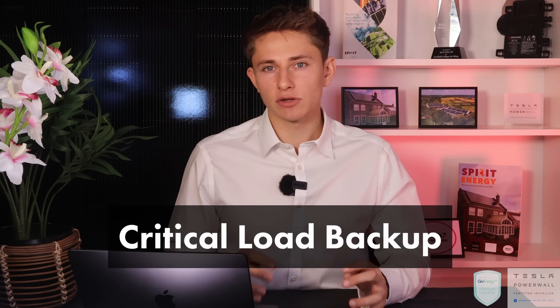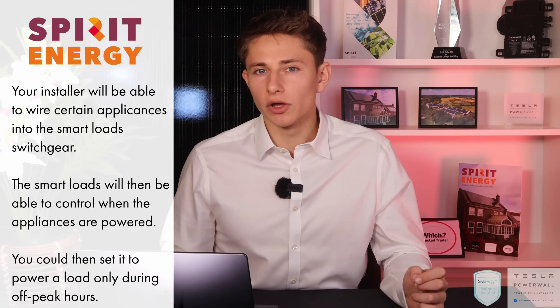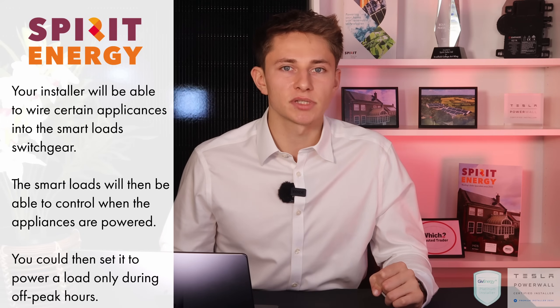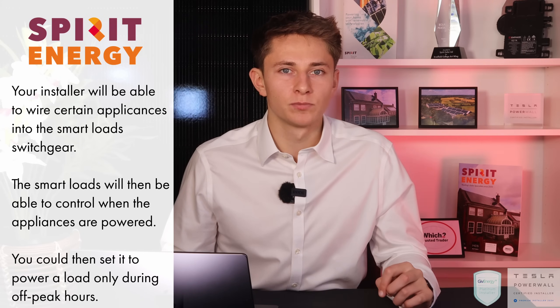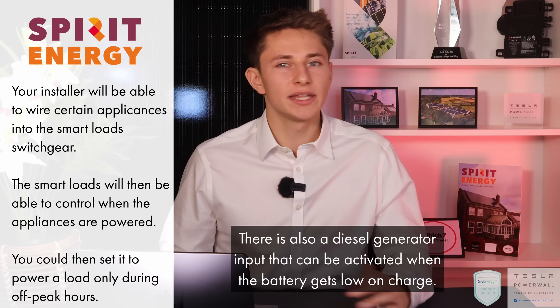The GivEnergy Gateway 2 has features which make it superior to the Tesla Gateway 2. Firstly, it allows for critical load backup, meaning you can keep really important appliances running longer in extended power cuts. When the battery drops to about 20% — or whatever you've set in the app — the Gateway stops powering all backup loads and switches to only power the critical loads. GivEnergy have also implemented Smart Loads, where you can set certain appliances to only run at certain times — for example, wiring an appliance into the Smart Loads switchgear and setting it to only draw power during your off-peak tariff window.